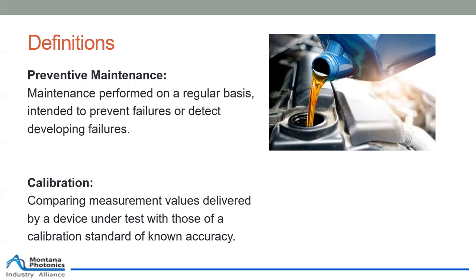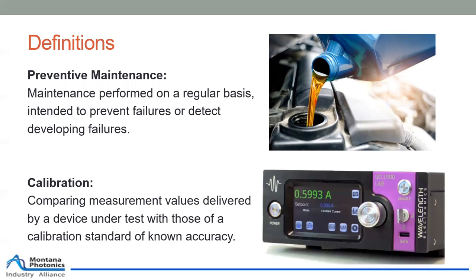Calibration is comparing measurement values delivered by a device under test with those of a calibration standard of known accuracy. For example, we build laser diode drivers that need to deliver a known amount of current to a laser. If I tell a customer it will deliver 5 amps, I need to measure the output with a calibrated multimeter to make sure it performs as expected.